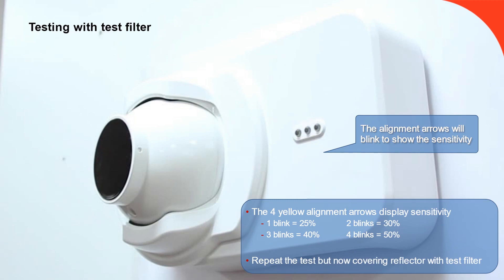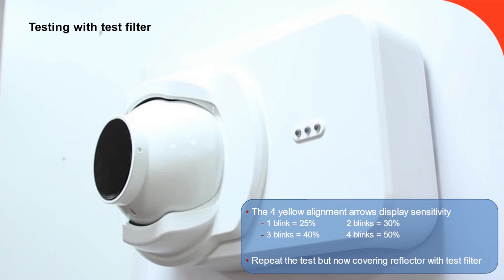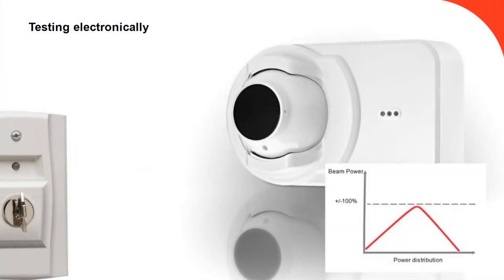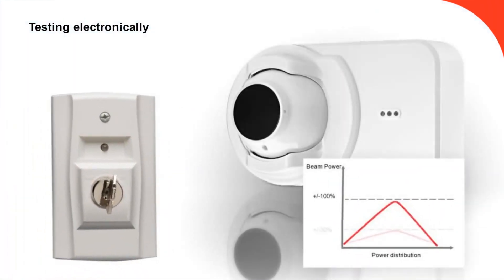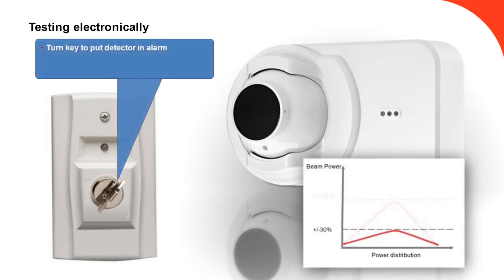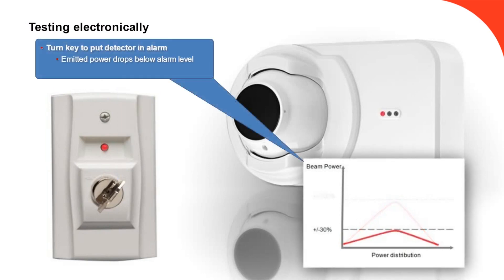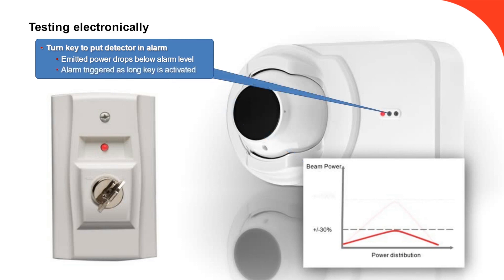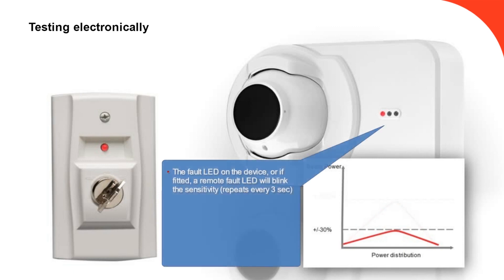Testing for faults can be done by covering the lens with a piece of paper; a fault should be generated within 60 seconds. The remote test key switch drops the emitter power, simulating an obscuration fire event. This is maintained for as long as the key is turned. Once reset, the device will run through its notification flash sequence at the detector, or at a dedicated remote fault LED, to indicate the sensitivity setting.